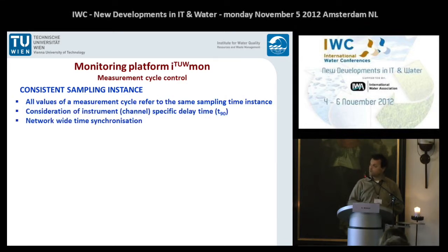Every measurement cycle is triggered at a specific time point, and all the instruments are running on this same time point. We even consider the time delay of the instruments. So if you have instruments with very long delay time, the whole cycle control considers this. And we have a network-wide time synchronization.